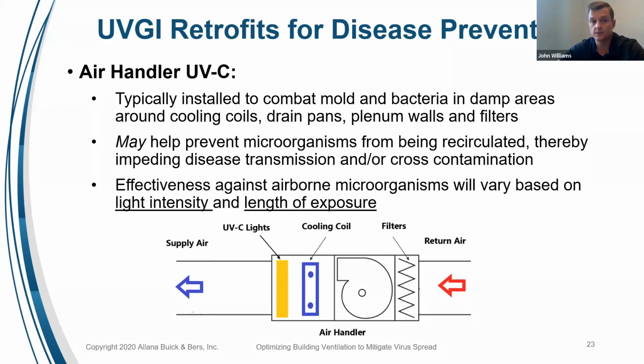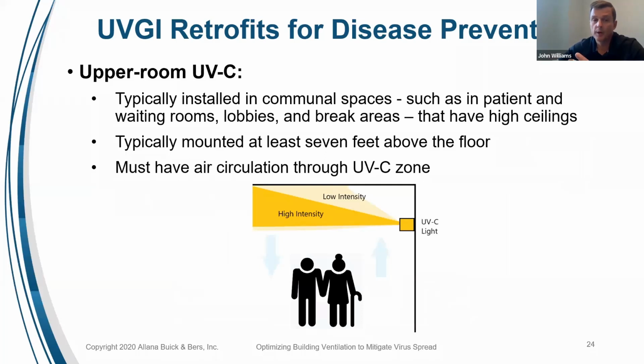So how do we use UV to kill off the coronavirus? A better application is upper room UVC. This is typically installed in the upper areas of a room. Because UVC is hazardous to people, it has to be installed above 7 feet. And then we have to be able to circulate air from the room up through that area, whether it's ceiling fans or returns in that area. We have some sort of air circulation in that room to promote the microorganism exposure into that high intensity UVC area up there.